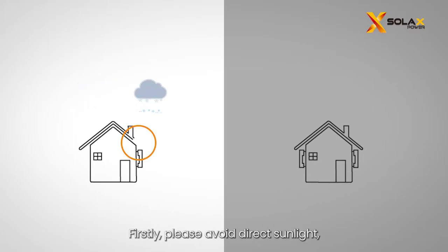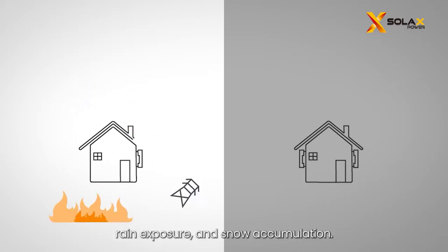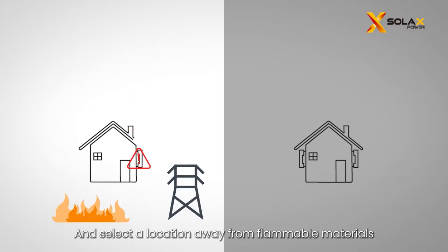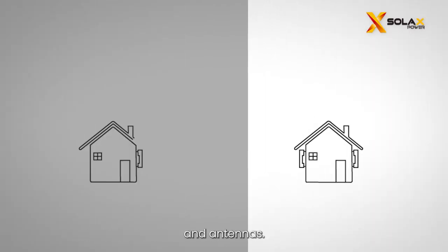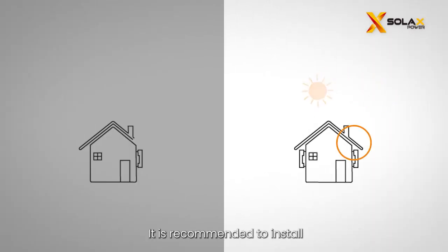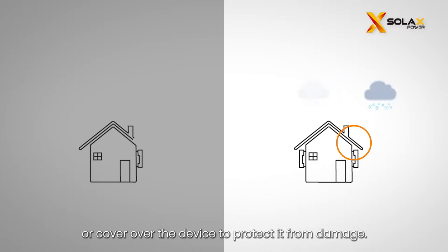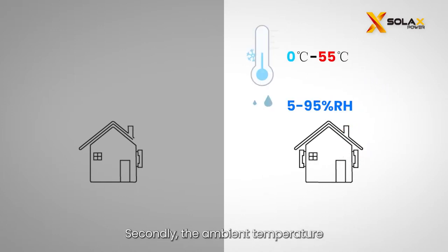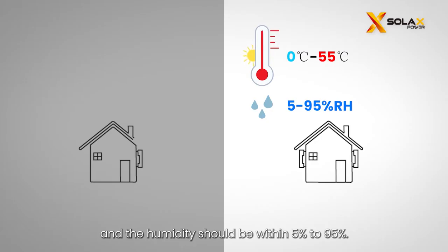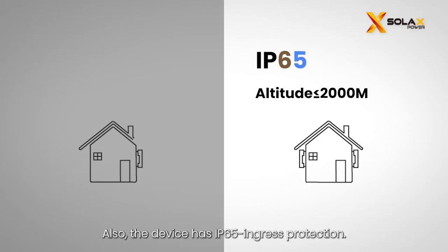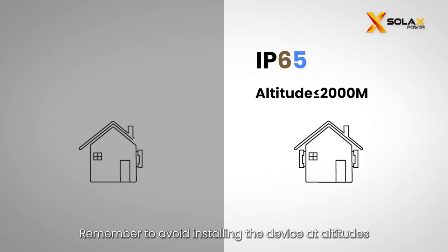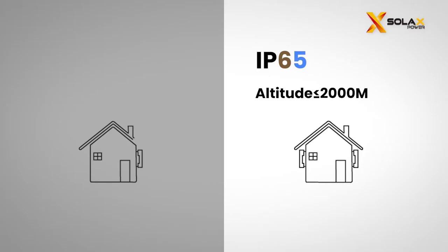Firstly, please avoid direct sunlight, rain exposure, and snow accumulation, and select a location away from flammable materials and antennas. It is recommended to install an awning or cover over the device to protect it from damage. Secondly, the ambient temperature should be between 0 degrees Celsius and plus 55 degrees Celsius, and the humidity should be within 5% to 95%. Also, the device has IP65 ingress protection. Remember to avoid installing the device at altitudes exceeding 2,000 meters.